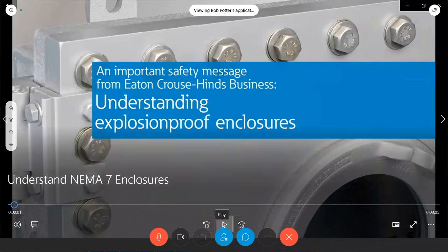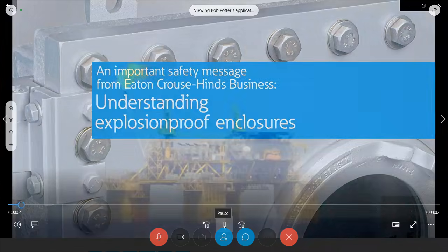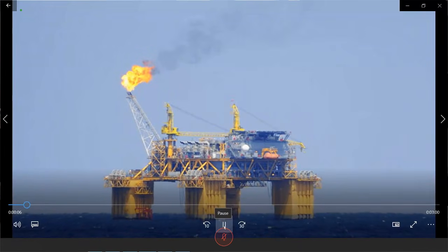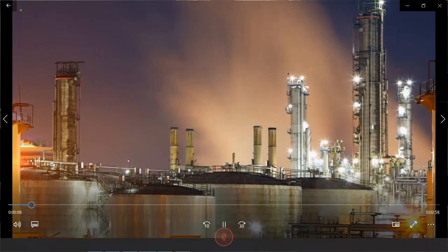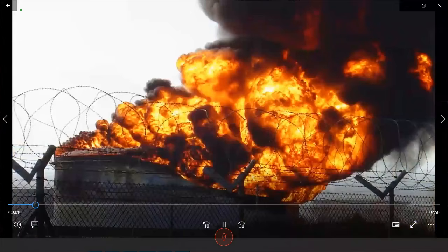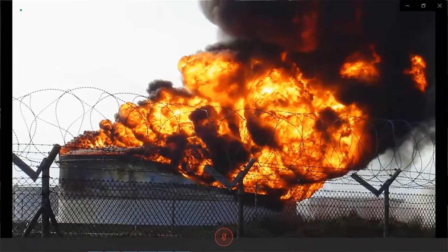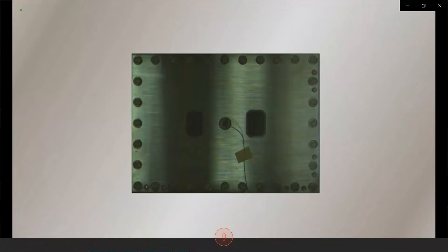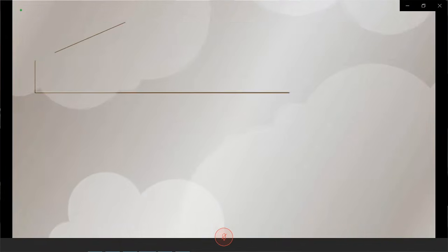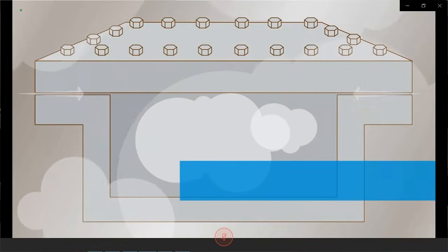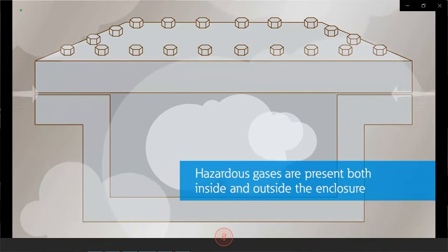Perfect. When it comes to explosion-proof enclosures in harsh and hazardous environments, failure is simply not an option. When it does occur, the consequences can be devastating. Because gases and vapors present in Division 1 and 2 areas will commonly enter explosion-proof enclosures, the NEC and CEC have set specific requirements regarding their design and installation.